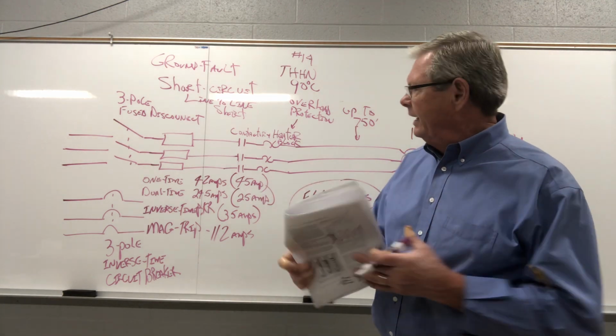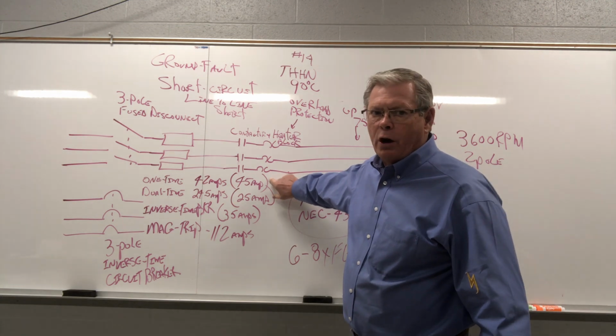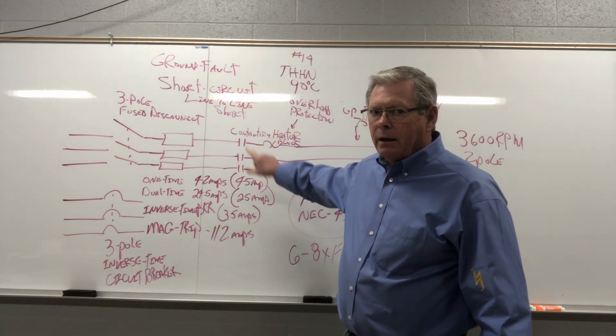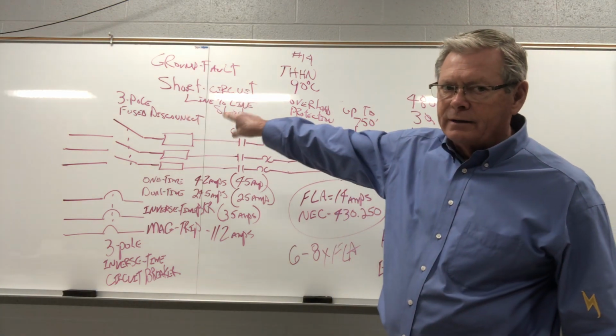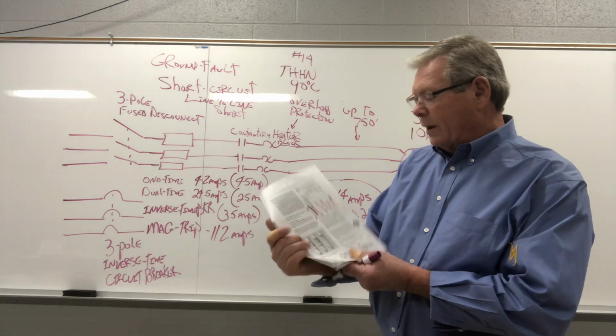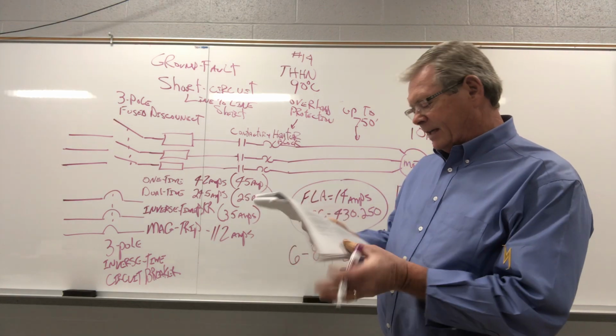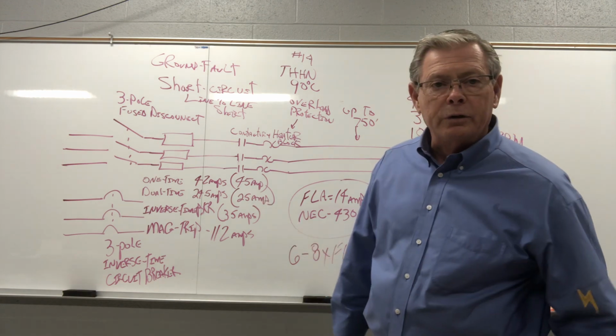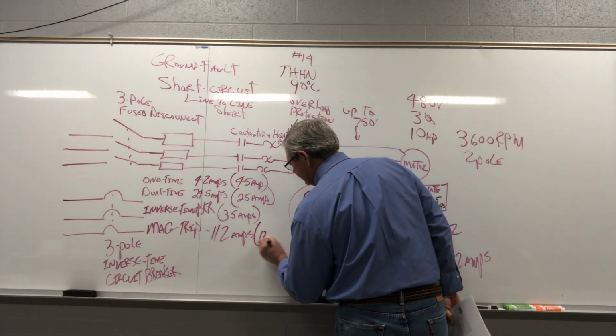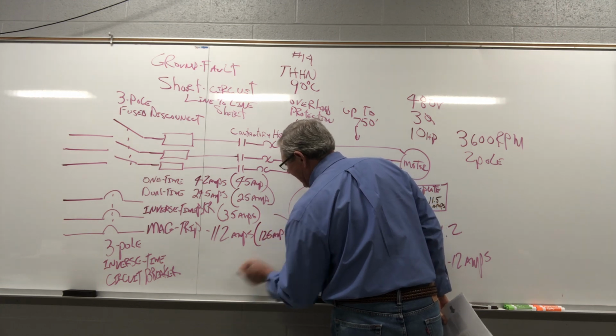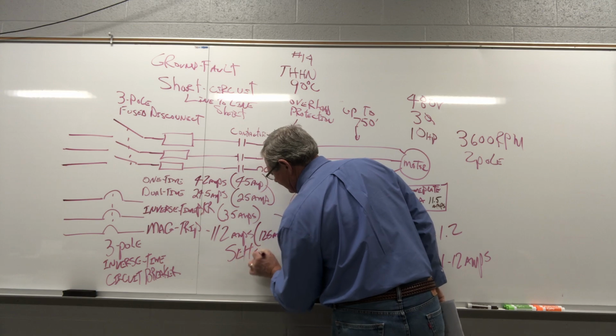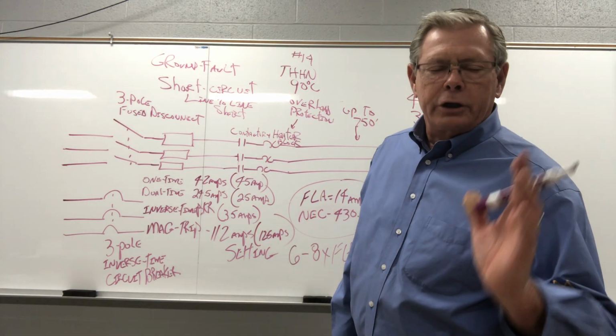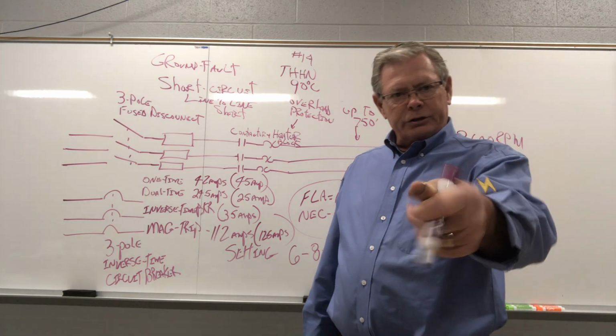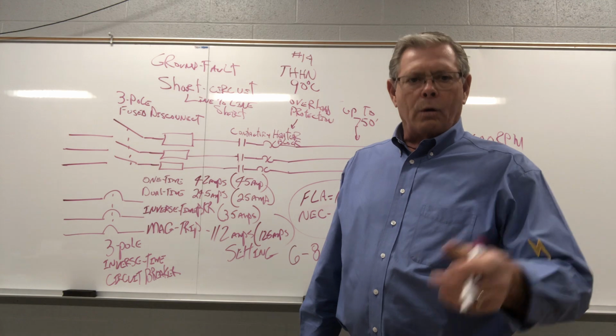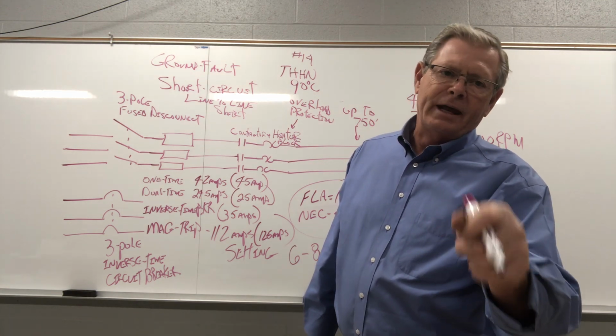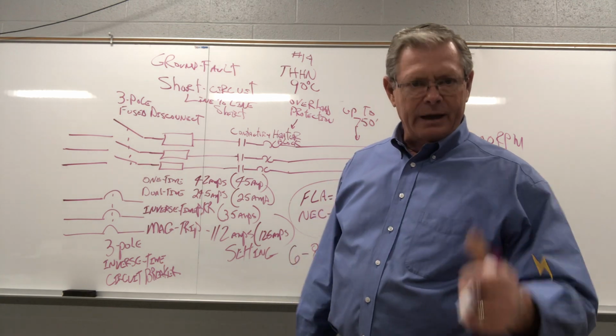So it makes sense whenever we split the overload protection out for the overload heater block. All that has to do is take care of line to line short, line to ground short. So 112 amps, is that a standard size? Nope, so we go to 125 amps. And that'll be a setting. That magnetic trip current will be a setting on the front of the breaker that you'll just turn a little notched dial, or sometimes it's not notched. So you'll just set it as close as you can to 125 amps and you're good.